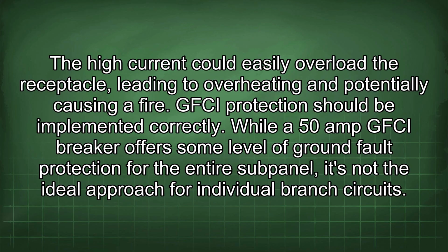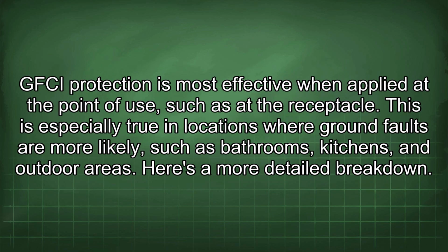GFCI protection should be implemented correctly. While a 50-amp GFCI breaker offers some level of ground fault protection for the entire subpanel, it's not the ideal approach for individual branch circuits. GFCI protection is most effective when applied at the point of use, such as at the receptacle. This is especially true in locations where ground faults are more likely, such as bathrooms, kitchens, and outdoor areas. Here's a more detailed breakdown.